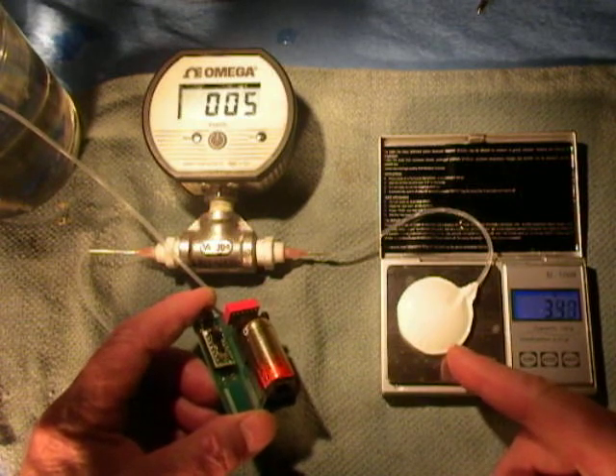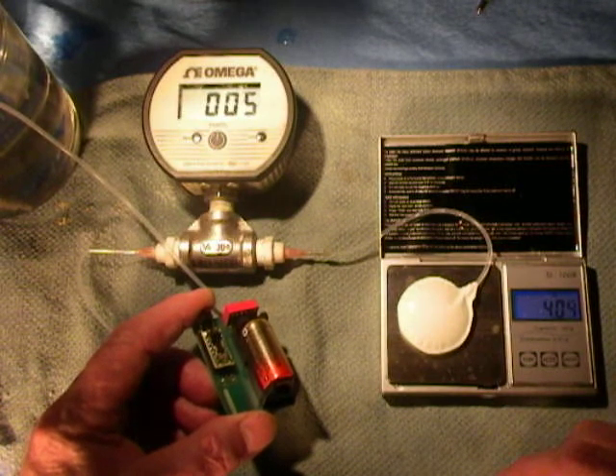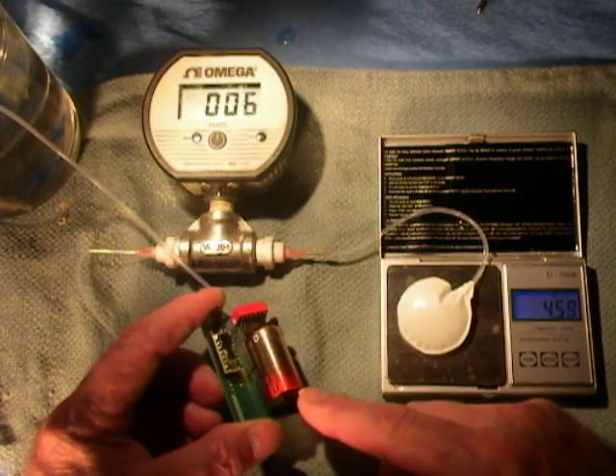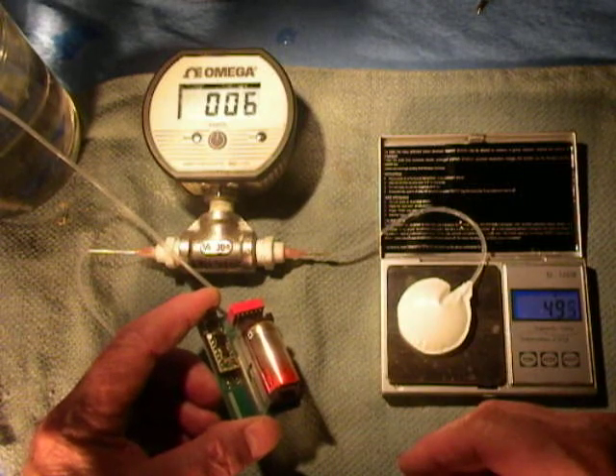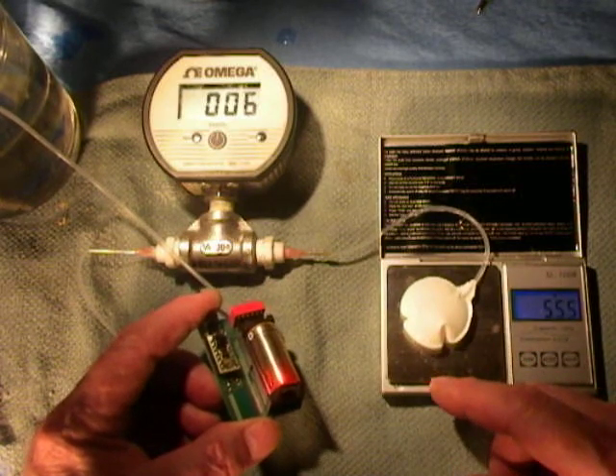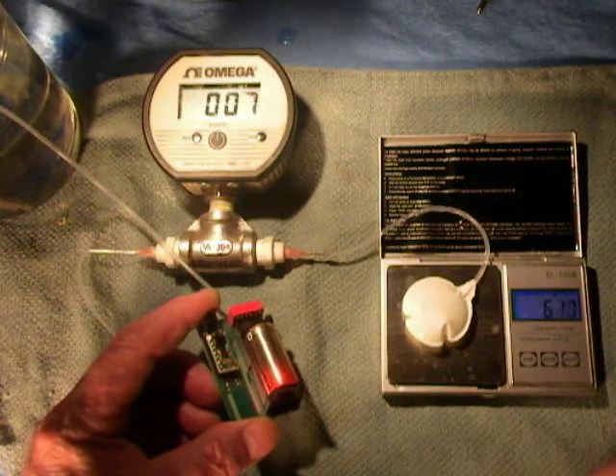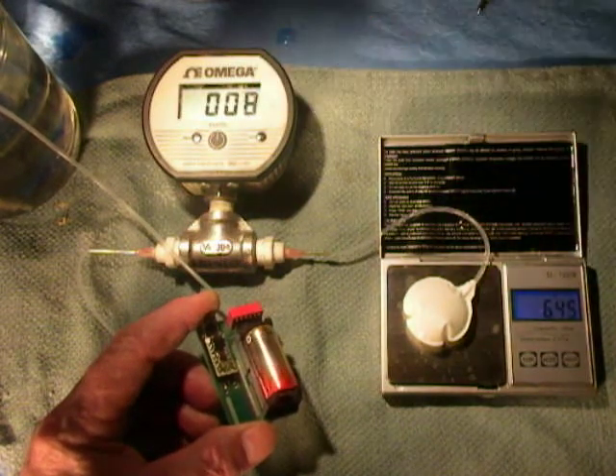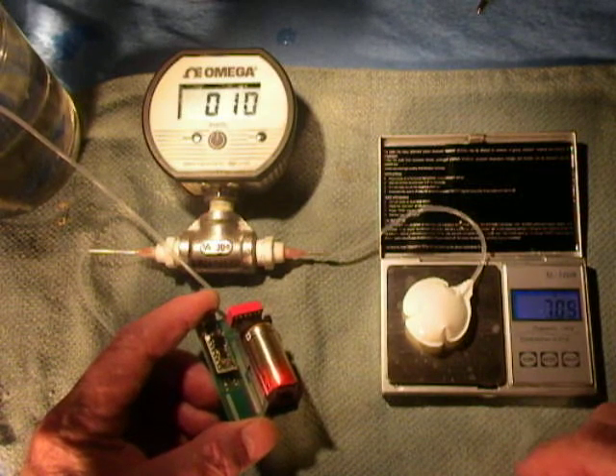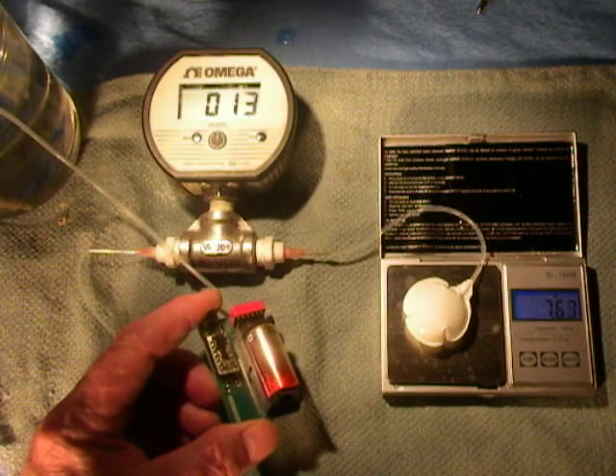These can serve as any type of scientific or medical application. They can serve as a reservoir for fluid that would be an input to the pump. This is chemically inert, so it can be filled with anything you desire. It's running about 10 cc a minute, and you'll watch the pressure come up to a plateau as the silicone balloon expands to its modulus of elasticity.